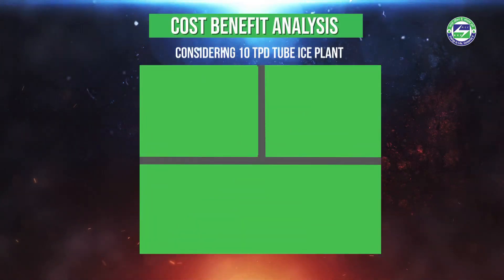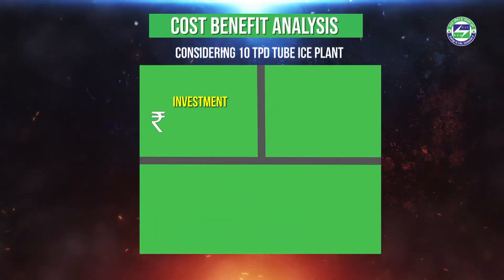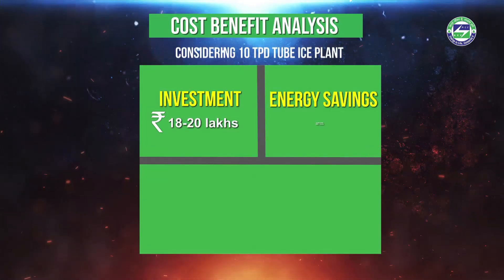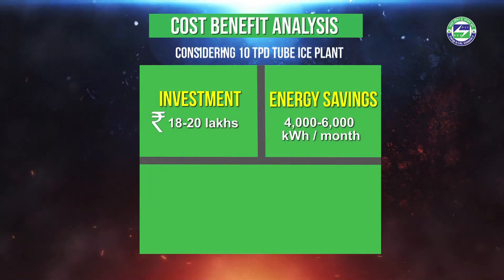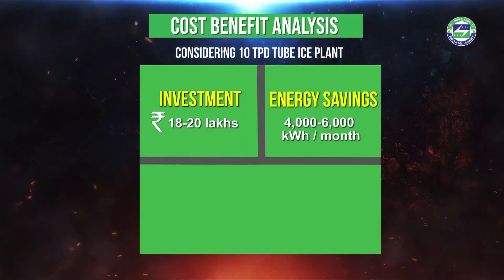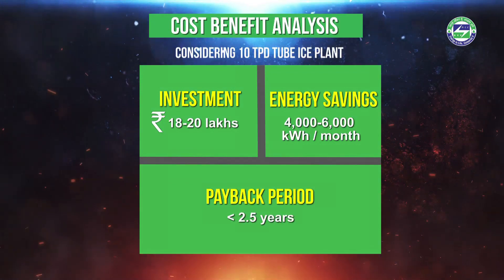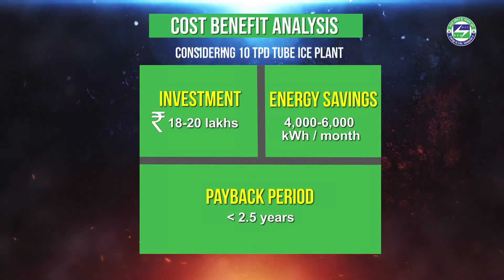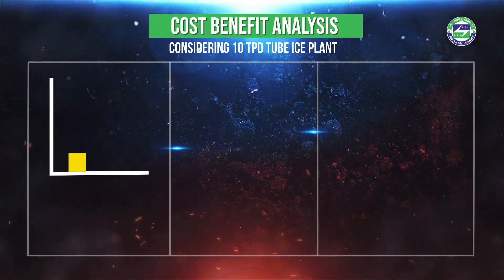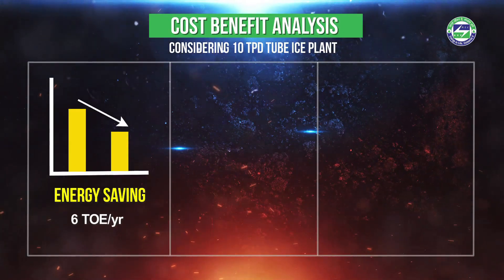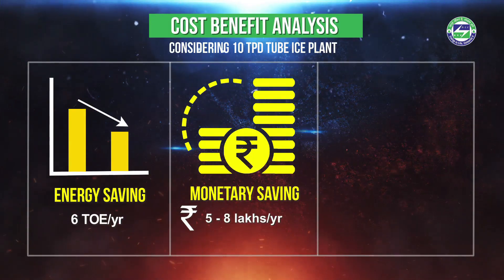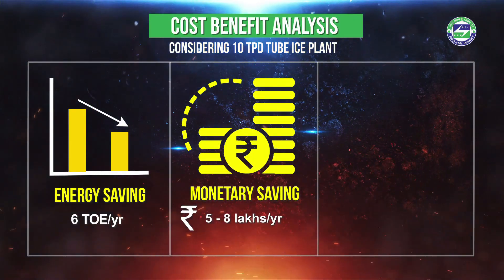For a 10 TPD tube ice plant, the investment required is 18 to 20 lakh rupees. The installation leads to a saving in electrical energy consumption of 4,000 to 6,000 kilowatt hours per month, and the investment can be recovered within 2.5 years. The installation leads to an energy saving of 6 tons of oil equivalent and a monetary saving of 5 to 8 lakh rupees per year.